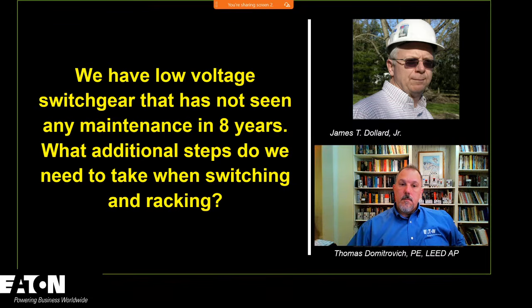So, for example, let's assume that this is service-supplied switchgear. And even with the change that we made in 230.71 in 2020, switchgear is fully compartmentalized, so you could have 6 disconnects in that switchgear. So let's assume it's 6 low-voltage power circuit breakers in switchgear, and they're telling us there's no maintenance in 8 years. When is maintenance required?